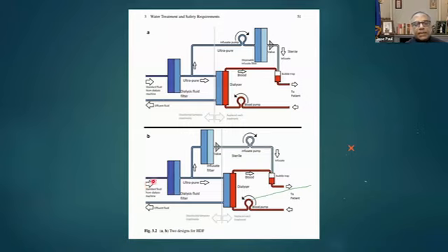The second technique is that the standard dialysis solution is generated by the machine. Again, here the filter is located pre-pump, pre-infusate fluid. Whatever the method, after the first filter, when the infusate is delivered back into the patient's blood, it has to go through another filter. That is the most important thing that you have to remember. Different manufacturers use either one of these techniques.